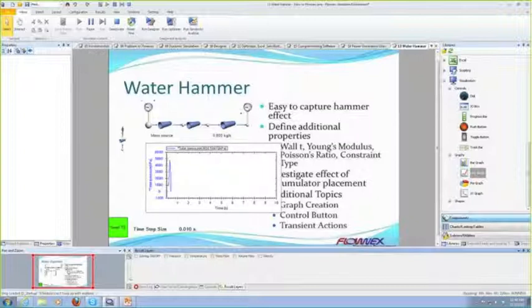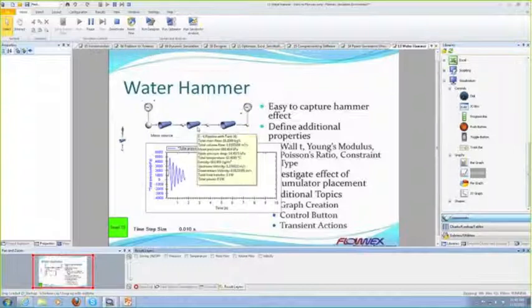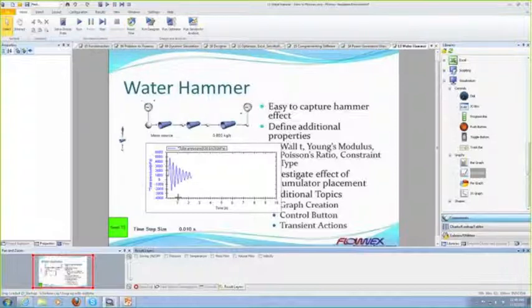we start to see these huge pressure spikes as the pressure wave travels back and forth and eventually dampens out. And so a thing to note here is that the working fluid in this model is just a single phase liquid representation. In reality, what's happening with these negative pressure spikes is we're actually going to be changing phases, because we're dipping below the vapor pressure.